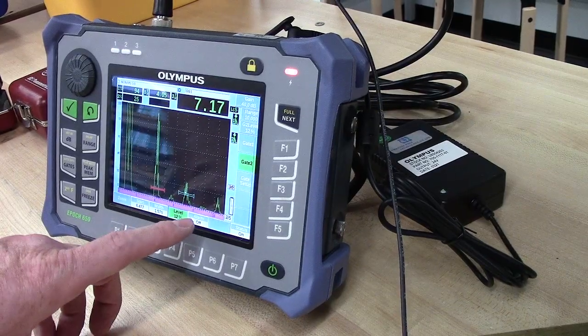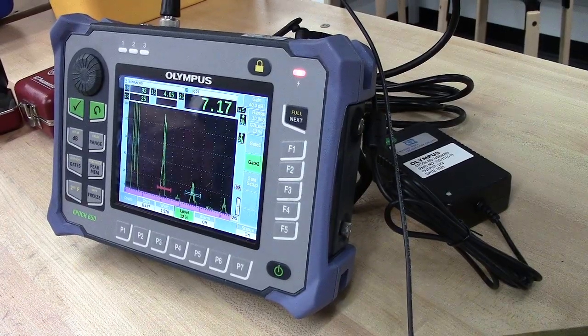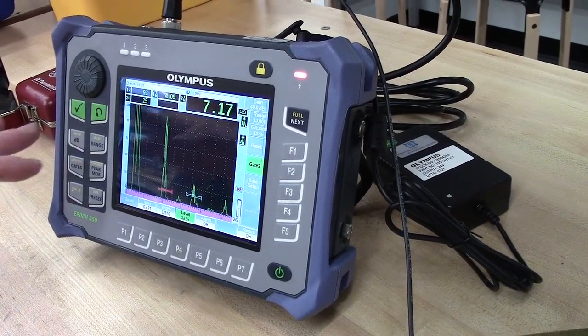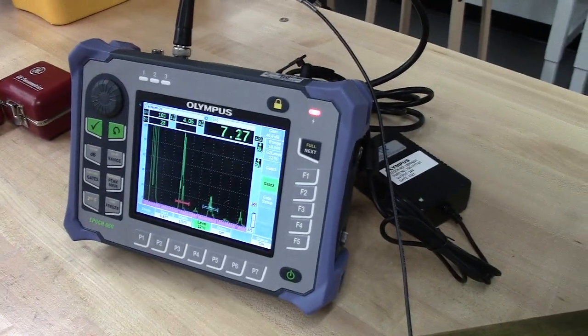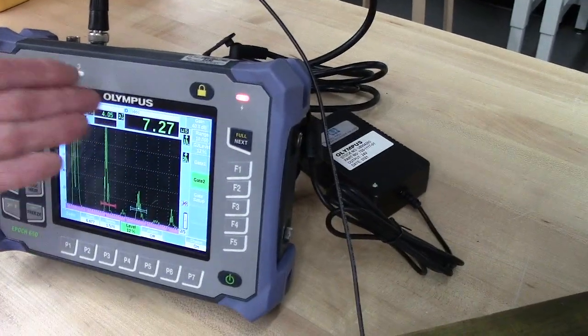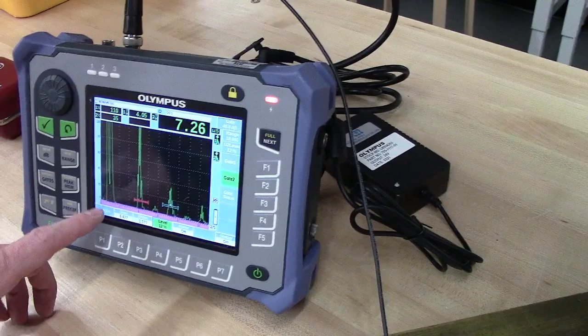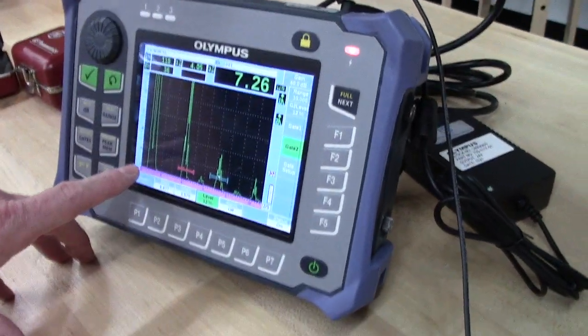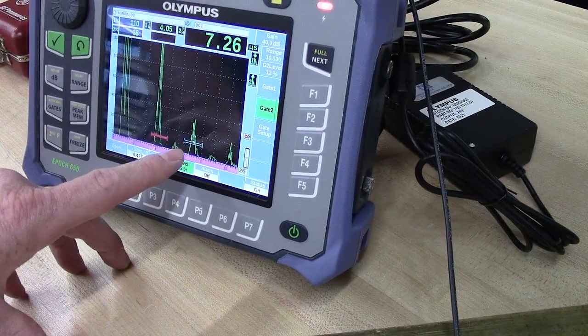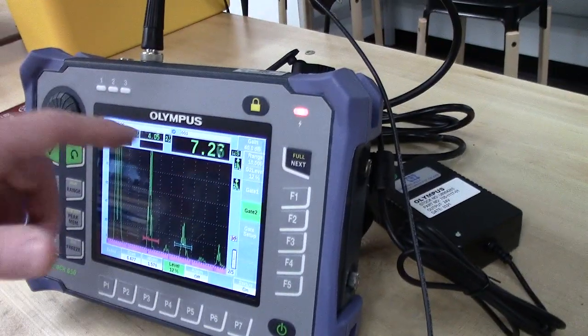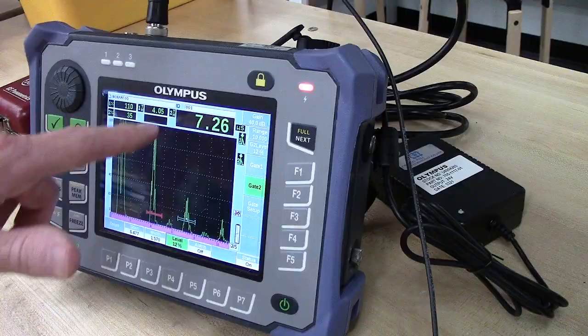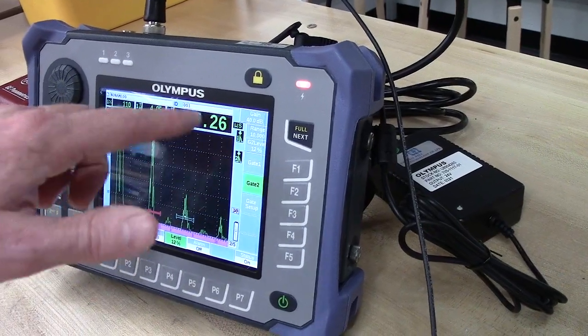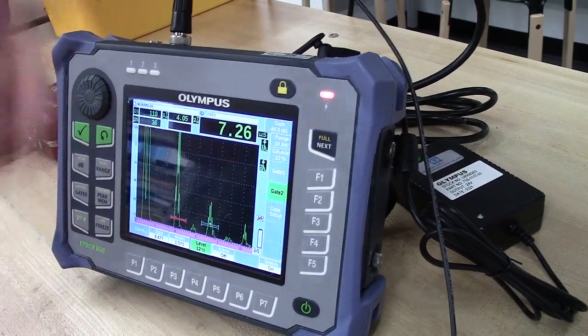The alarm, we can set it to be like a minimum value. Or if it drops below a certain value, it'll give us an alarm. But the only thing that we need to do at this point to get the right measurement out of this is, so you look up here and you might think that 7.27 microseconds is the time. But if you look here, this is more the time. It goes from 0 to where the second gate is. And this might not be so clear, but the fact that this is saying 2 here is indicating that that's what it's doing. But we can also see that just based on the value. But what we actually want is the time between echoes.